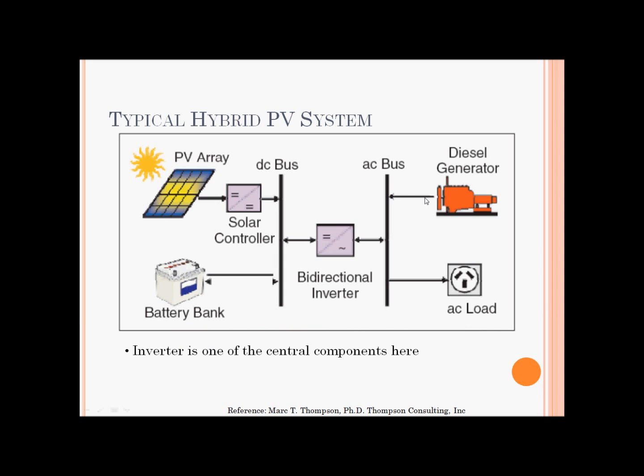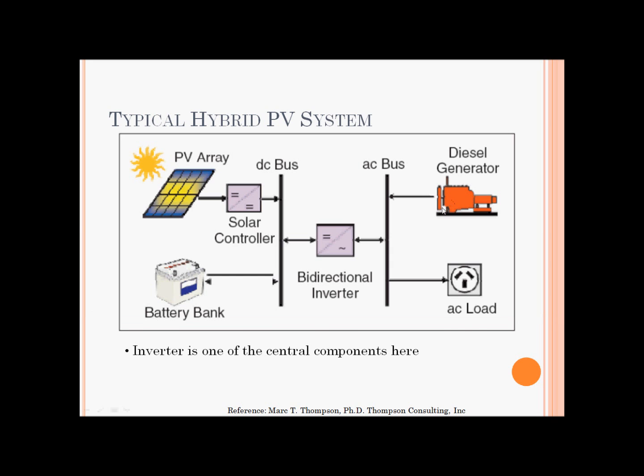As you can see, if the line goes out and somebody is working on the line, but the photovoltaic system is still selling energy to the line, anyone working there will be electrocuted. So the inverter needs to be smarter and know when to shut off and when to turn on. They are more complex because they can provide power from photovoltaics to the load, and they can also provide power from a diesel generator on the AC bus to the battery bank.